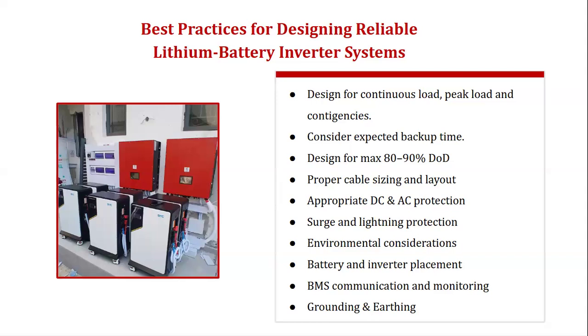The first one is design for continuous load, peak load, and contingency. During survey, when you measure your load, you already know before you deploy an inverter system or battery what capacity is needed, what the load capacity is, and how they want to use it.